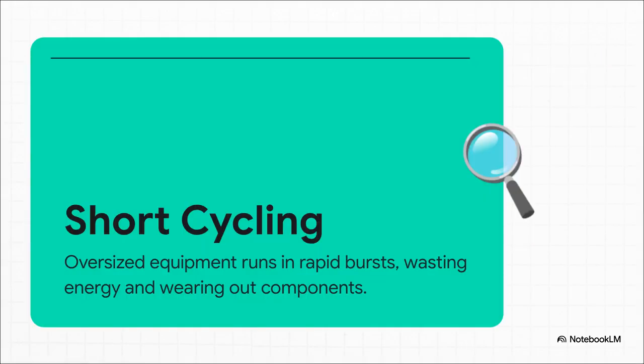So to combat these extremes, homeowners often buy oversized equipment, which leads to something called short cycling, a massive waste of energy that destroys the machinery from the inside out. People think, it's freezing here, I need the biggest furnace possible. But if you don't do a proper Manual J load calculation, basically the math pros use to match equipment size to your home's exact cooling needs, the system blasts heat, satisfies the thermostat in minutes, then shuts down abruptly, only to turn back on again a few minutes later. This rapid on-and-off cycling ruins efficiency and tears the components apart well before their time.